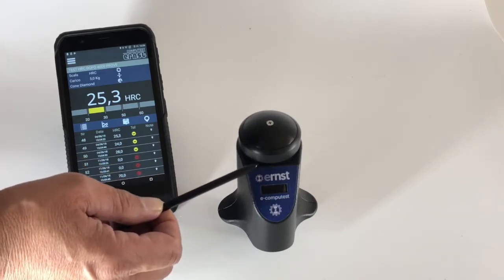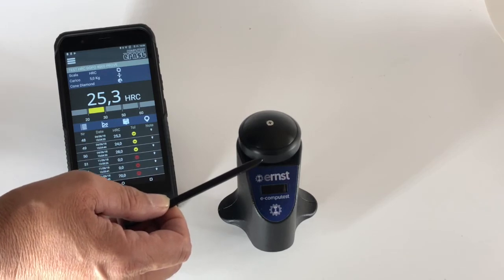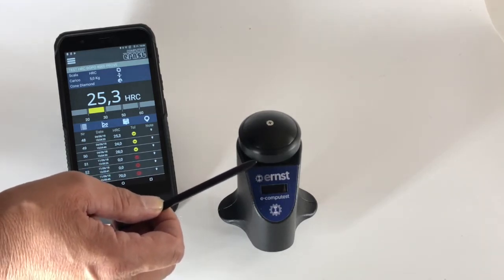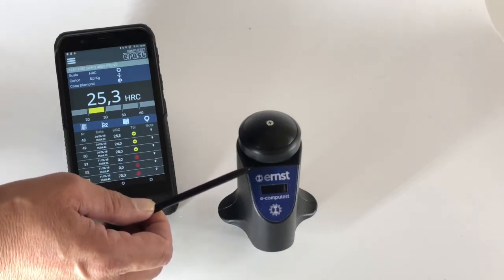The repeatability of the instrument is up to, I would say, better than one percent or plus minus 0.3 HRC.